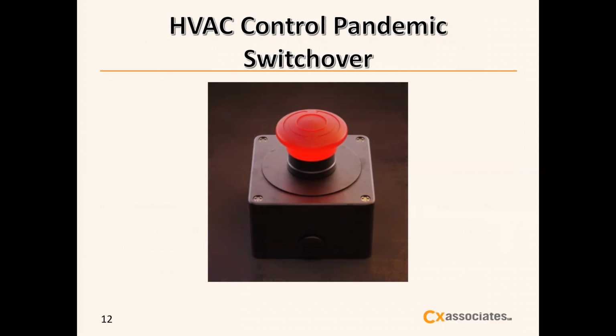So when we get back to our real normal, it will be our job to ensure the building returns to its optimized operation we had implemented in the 2018 retro commissioning project. With that in mind, and because it would be a shame to have lost all of the efficient programming of the mechanical equipment we developed, the controls programmer from Temperature Controls of Vermont developed the pandemic sequences under a new mode, and we implemented a pandemic mode button on the controls interface so that the building operator can easily go between the efficient mode and the pandemic mode of control sequences. Hopefully we won't need this for future pandemics or epidemics, but it's there if we do, and we don't have to recreate it or the efficient operation.